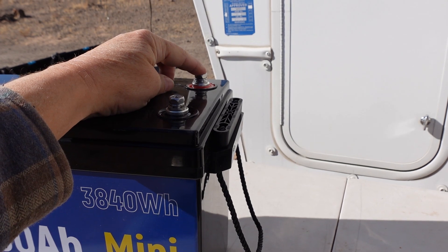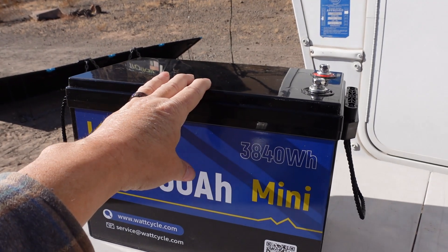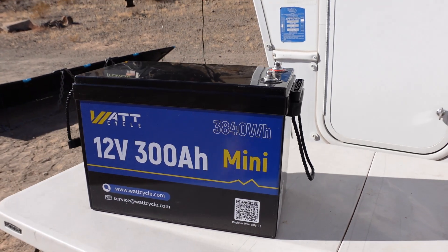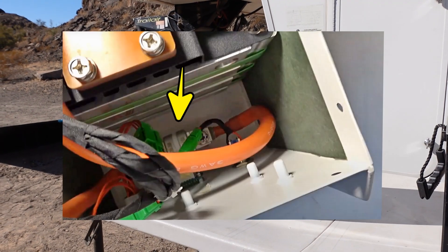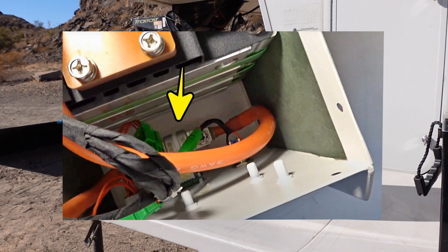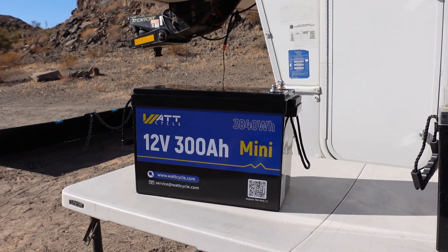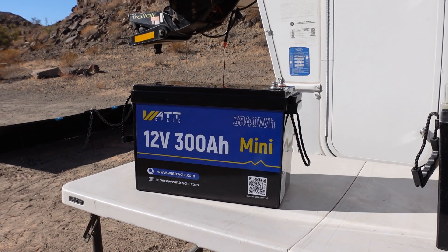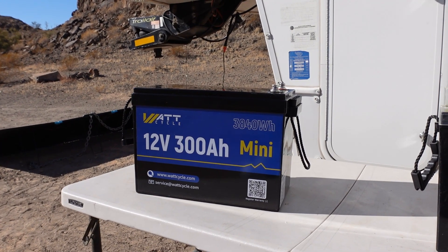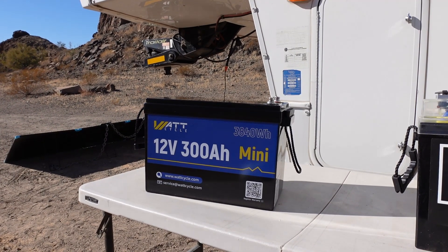Good practice is to always put a fuse on every battery to protect the wiring and not count on the battery's internals as your shutdown. Some of the very high-end batteries like my Xantrex — when I opened it up — actually had a proper 250 amp fuse inside. So they put an internal fuse in case the customer doesn't fuse it properly on the outside, which is a nice touch. That's the reason you pay more — there's always a trade-off with cheaper batteries.